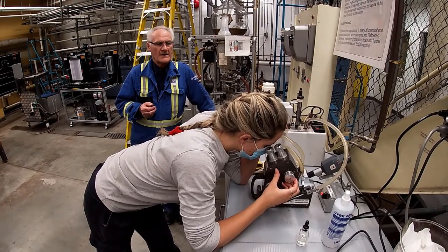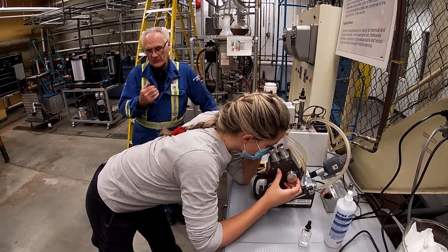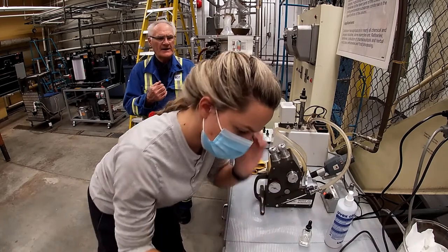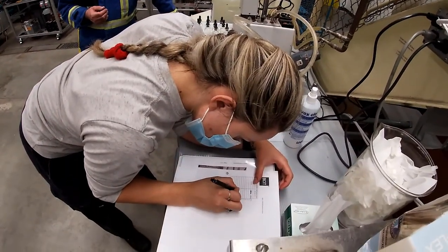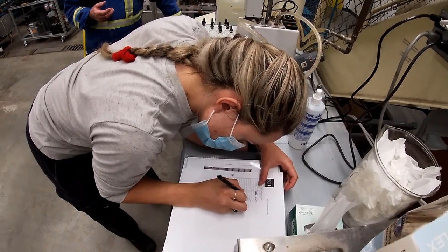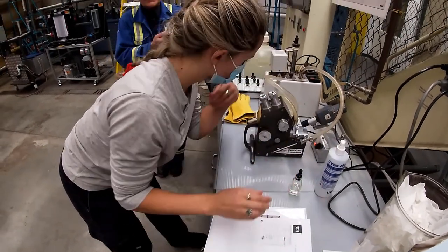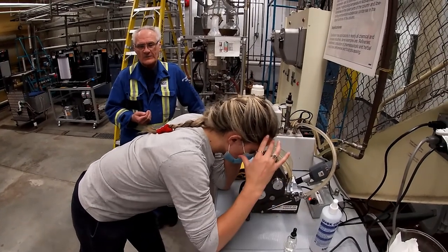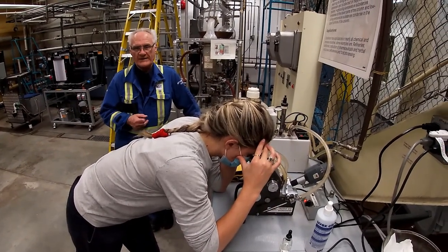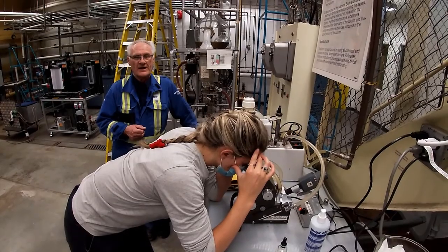Okay, so she's checking the upper glass to look for where the line is moving, and then adjusts the refractive index knob, the lower of the two knobs, until she gets the line to go through the crosshairs, and then once it's through there, she reads off what the value is to the 4th decimal. Thank you.